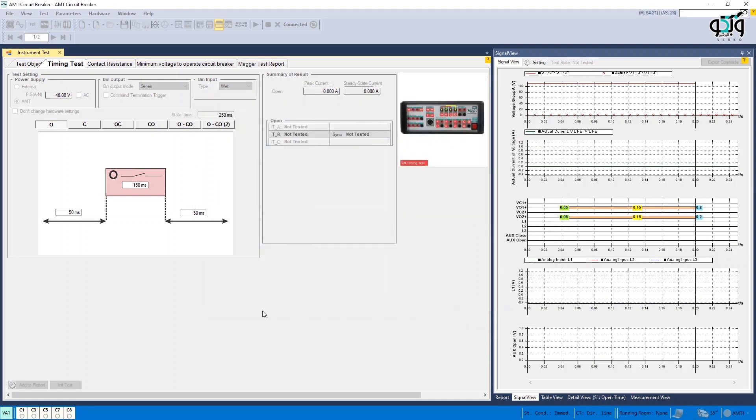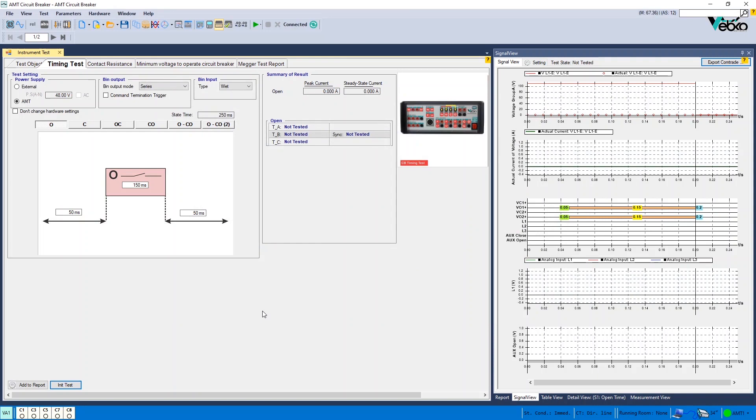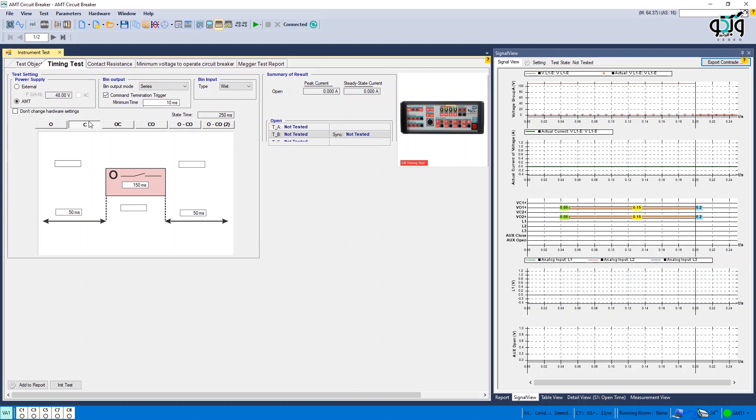The second point is that when you enter 150 milliseconds as the command time, this means that the command voltage is kept on the bobbin for 150 milliseconds. If you check Command Termination Trigger option and enter 10 milliseconds as the minimum time, the command is removed from the CB 10 milliseconds after its operation.